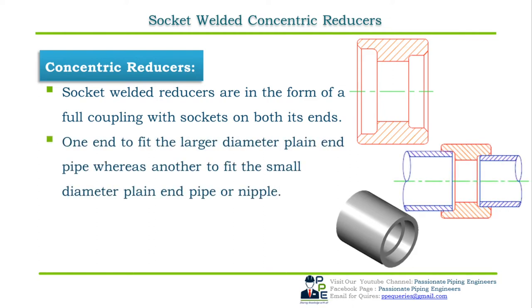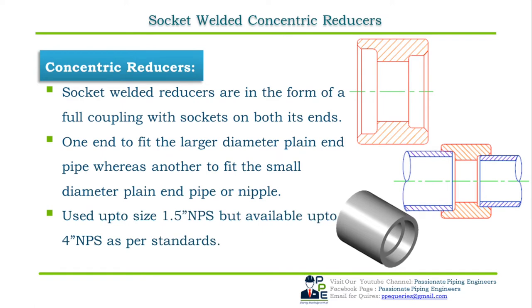Socket welded concentric reducers are in the form of a full coupling with sockets on both ends; they are also called reducing couplings. One end is formed to fit the large diameter plain end pipe, whereas the other fits the small diameter plain end pipe or nipple. They are used up to line size 1.5-inch NPS but are available up to 4-inch NPS. The dimensional standard is ASME B16.11.